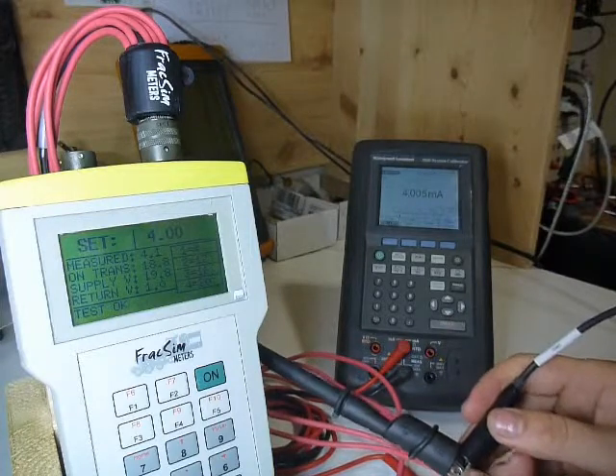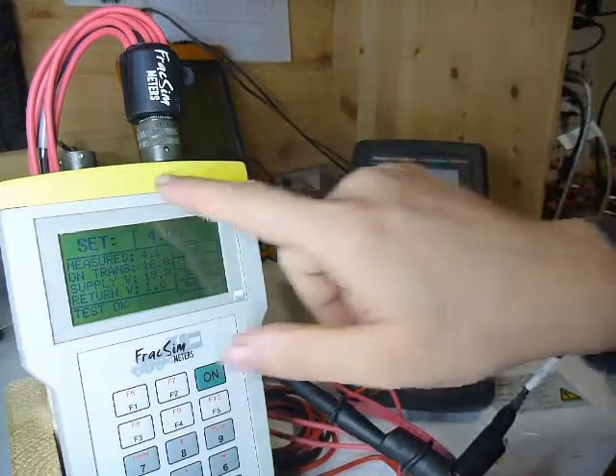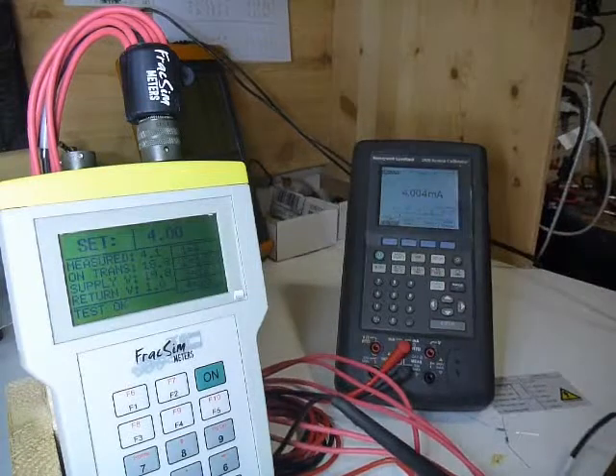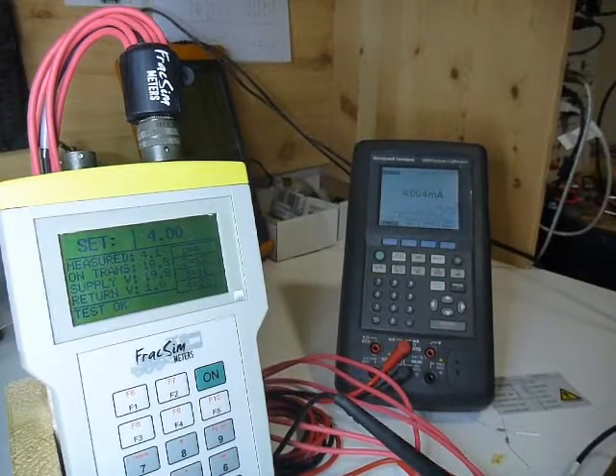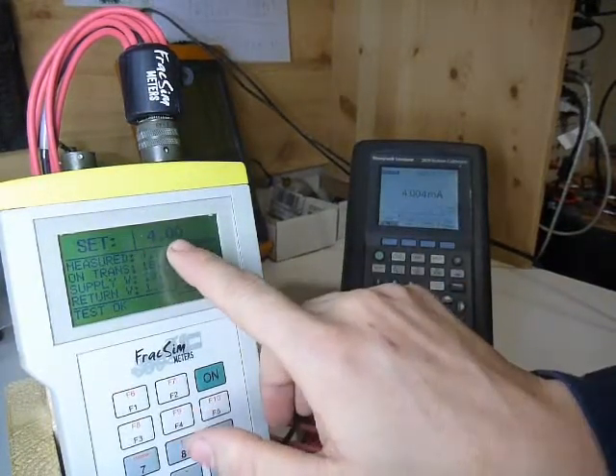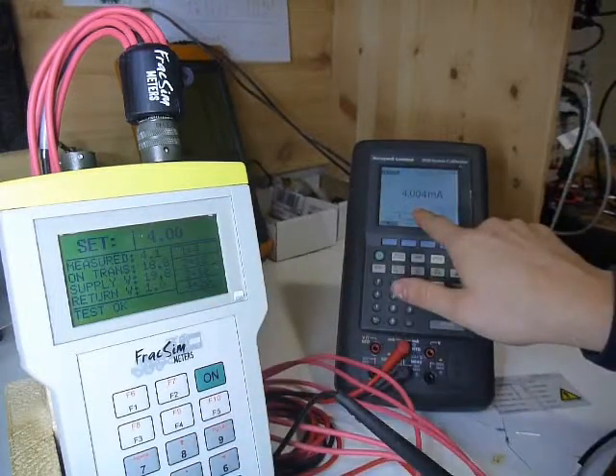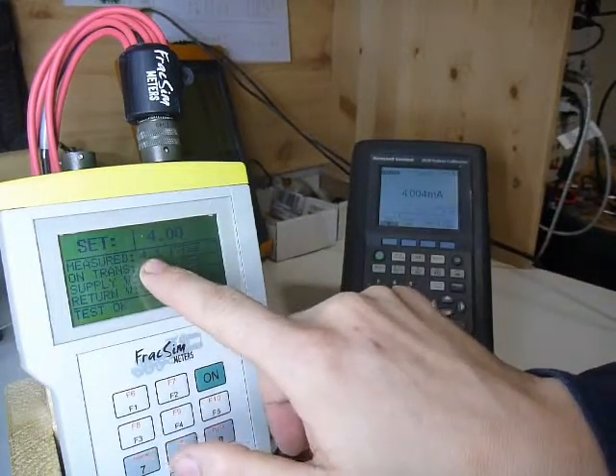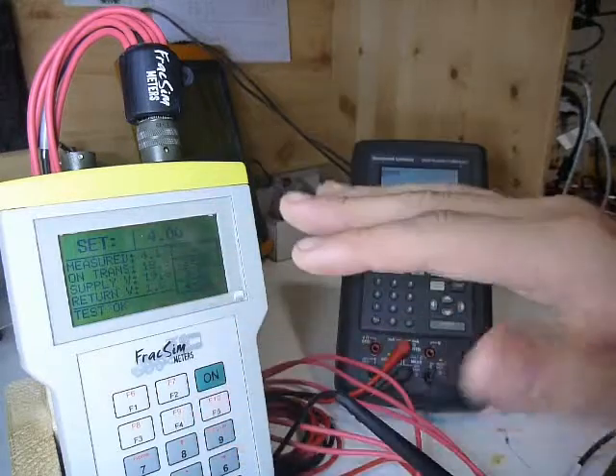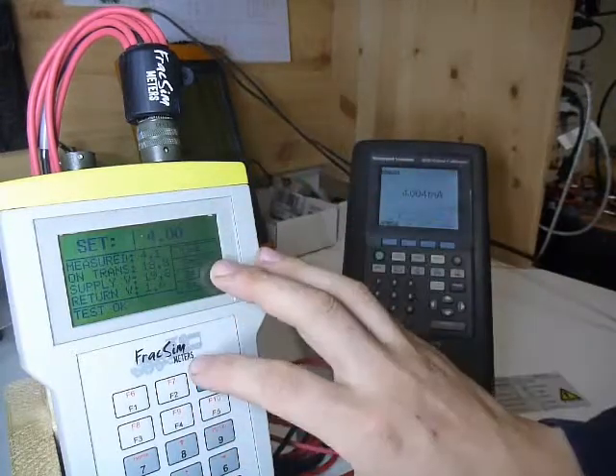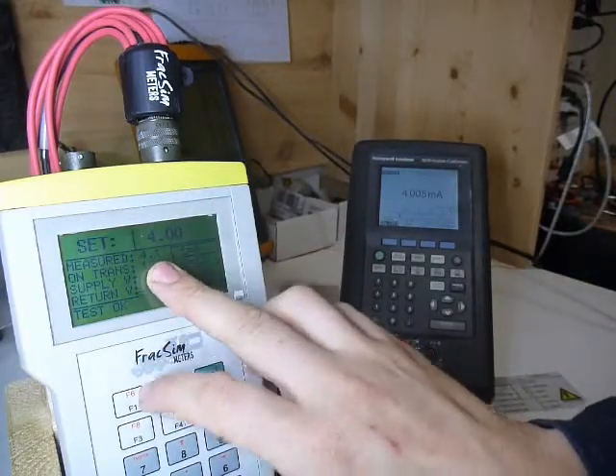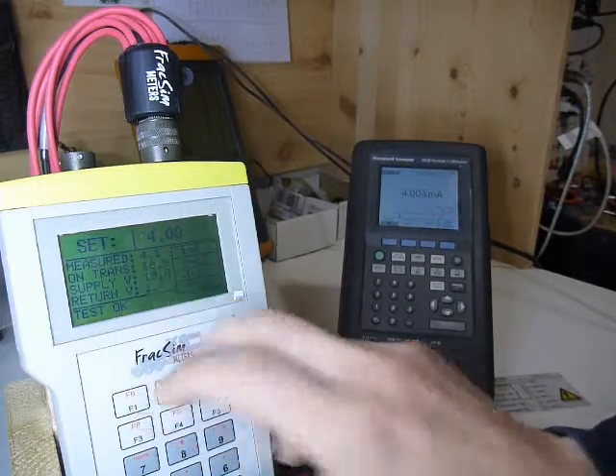So as soon as I hooked that up, you saw that went to 4 milliamps and everything kind of came in line here. So let's look what we got going on here. We got 4 milliamps is our set point. Our measured is 4.1. Now that measured, because of the way everything's working internally in the meter, is not quite as accurate, but it'll still give you an approximate value.